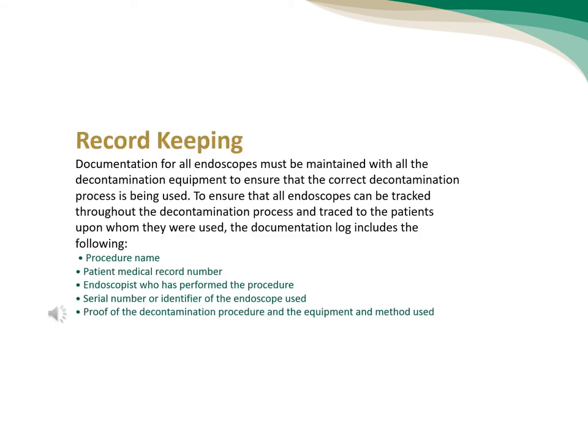Record keeping: Documentation for all endoscopes must be maintained with all decontamination equipment to ensure that the correct decontamination process is being used. To ensure that all endoscopes can be tracked throughout the decontamination process and track the patient on whom they were used. The documentation log includes: procedure name, patient medical record number, endoscopes used on the patient, serial number or identifiers, and proof of the decontamination procedure, equipment, and method used.